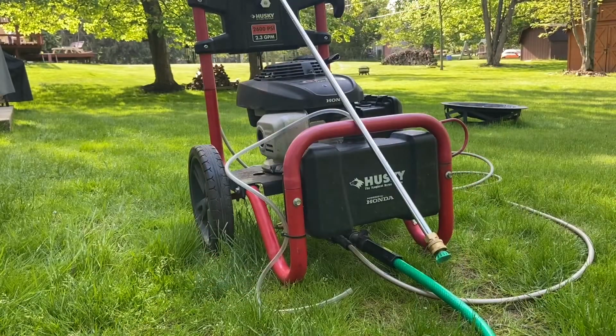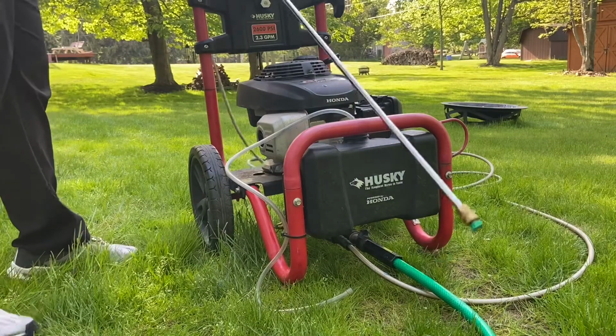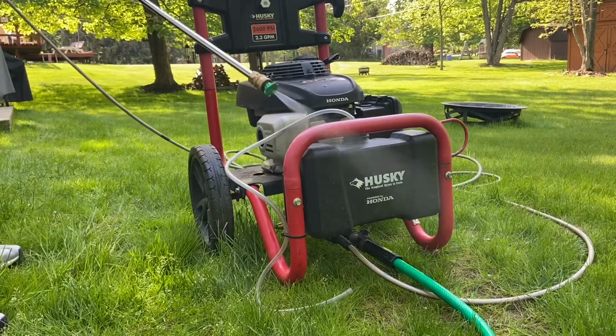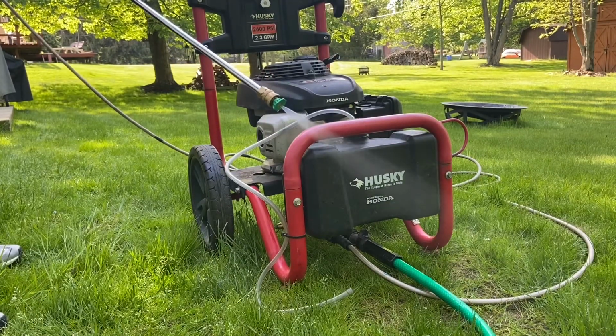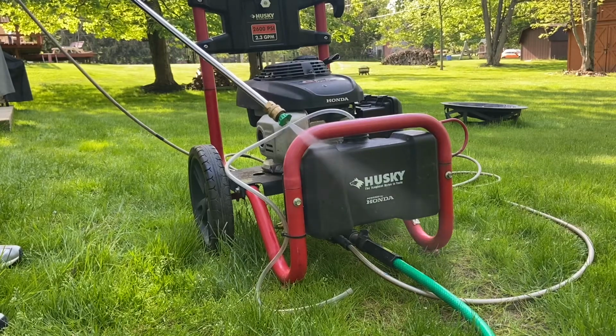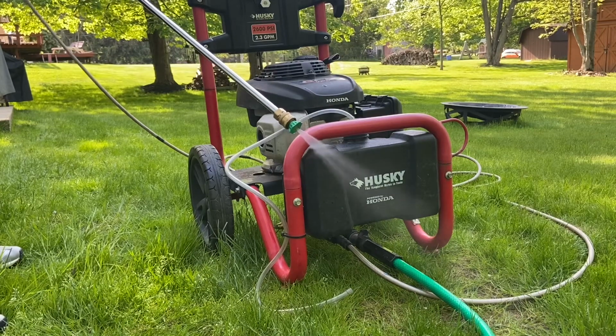Next question: why did that get damaged? A combination of use, improper storage, and you always need to make sure water's running through the pump, because those seals will overheat, and so will the valves.